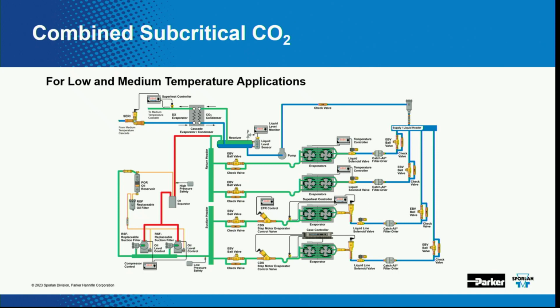Now what I'm depicting here is a combination of those two things I already showed you. On the top end, these are going to be our medium temp, and these don't require compression. They just have that pump circulating the liquid, taking it back out, separating the saturated liquid, and circulating that around. So that's our secondary CO2.